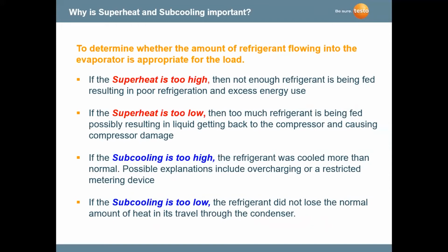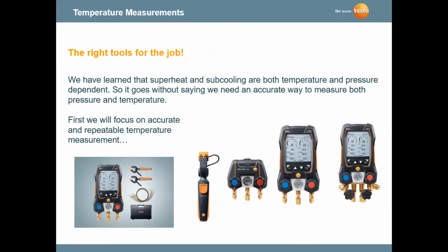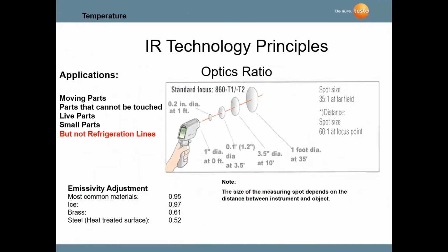If superheat is too high, there's not enough refrigerant being fed, resulting in poor refrigeration and excess energy use. If superheat is too low, you can see what happens there. Subcooling is too high and subcooling is too low. These are just some general conditions on what to do when you're getting readings that are not within the specifications of the equipment. That's another reason why our tools are changing, because the specifications of the equipment are getting tighter and tighter.